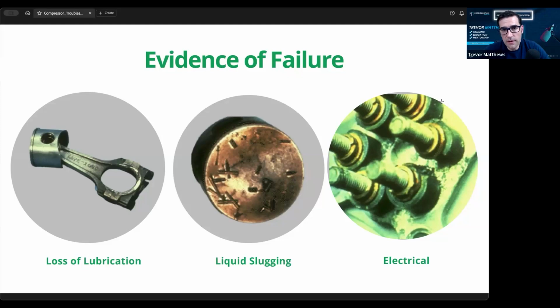As well as dual voltage motors, the 230 and 460. You've got to check how you're wiring that up, because that's so important. If you wire it up for a 230 volt motor, and then you put in a 460 motor, you wire it up to 230 and you hit it with 460, that compressor is in trouble. At the back of every compressor electrical plate there will usually be the wiring diagram, so it'll show you. But take a picture. Most of us have phones today. Take a picture, just like we were talking about, and mark out those wires so you know, because sometimes you have to pull off that electrical box to get that compressor back in, but you need to know those terminals that you need to put it on. So important.